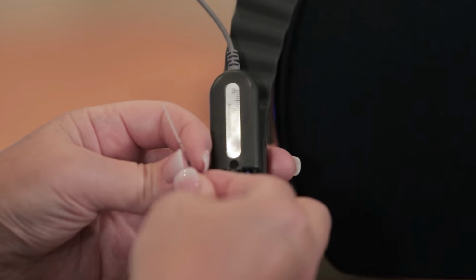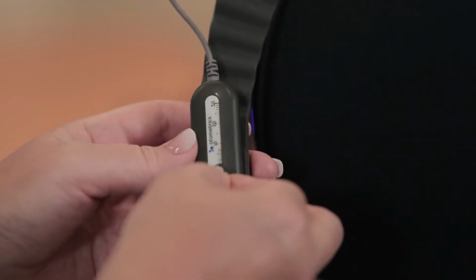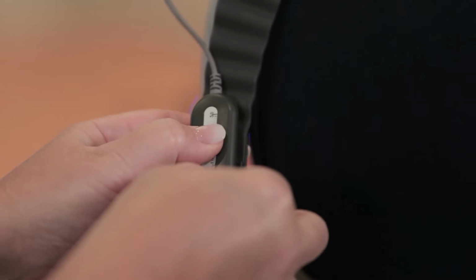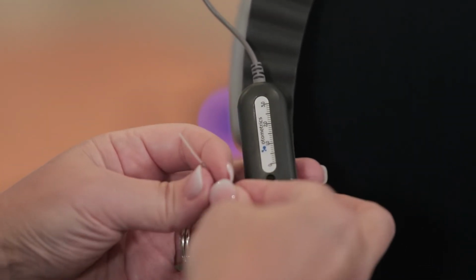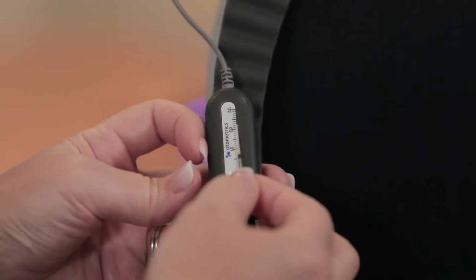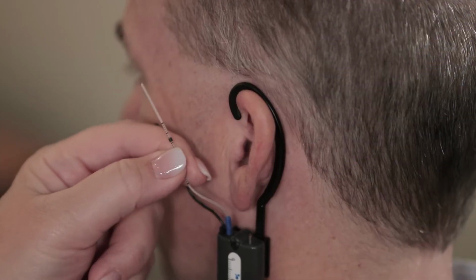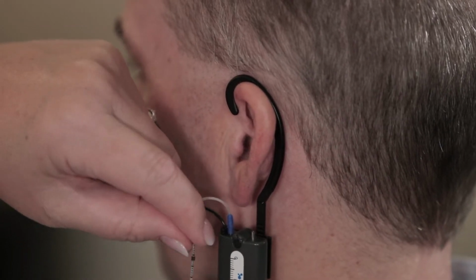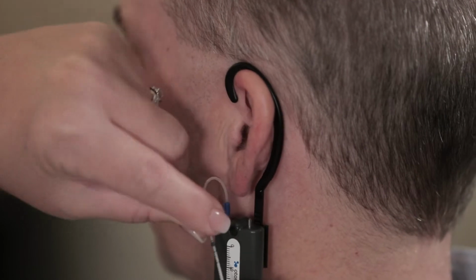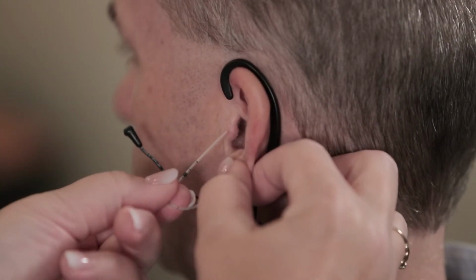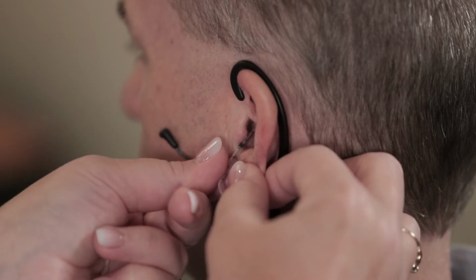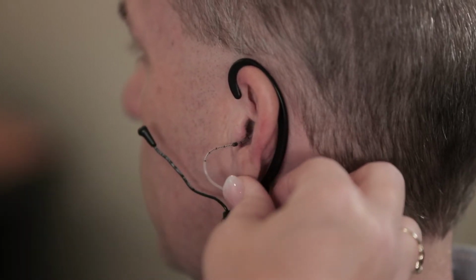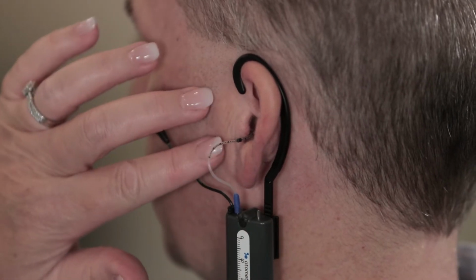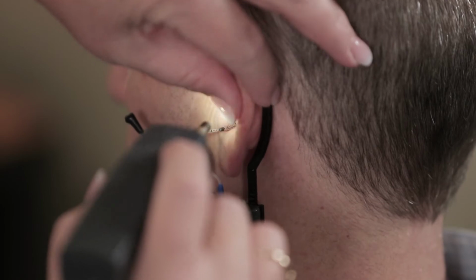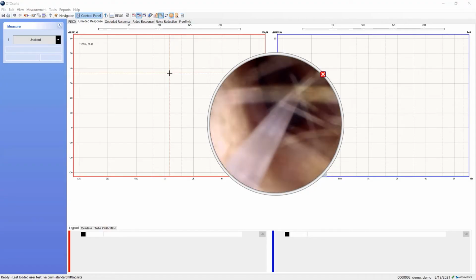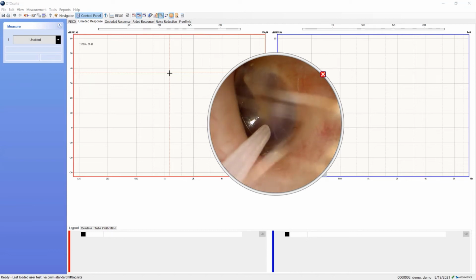Prior to placing the probe tubes into the client's ear canal, it is recommended to move the marker on the probe tube to the desired length. Look on the side of the probe. You'll see a small ruler. On the tube, there is a small black marker that slides up and down the tube. Using the small ruler as a guide, position the end of the tube at 30 mm, since our client in this demonstration is male. Slide the black marker down the tube until it reaches the 0 mm position. Insert the probe tube into the canal, just far enough so that the black marker sits in the intertragal notch at the opening of the ear canal. You can do a quick check with otoscopy to visualize the location of the end of the tube in the canal to see just how close it is to the eardrum.